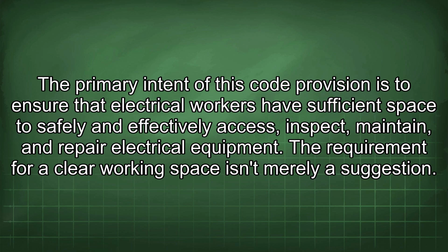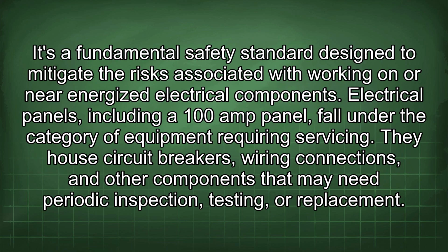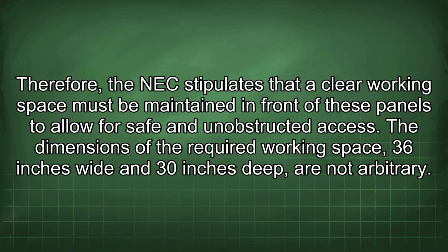The requirement for a clear working space isn't merely a suggestion. It's a fundamental safety standard designed to mitigate the risks associated with working on or near energized electrical components. Electrical panels, including a 100-amp panel, fall under the category of equipment requiring servicing. They house circuit breakers, wiring connections, and other components that may need periodic inspection, testing, or replacement.